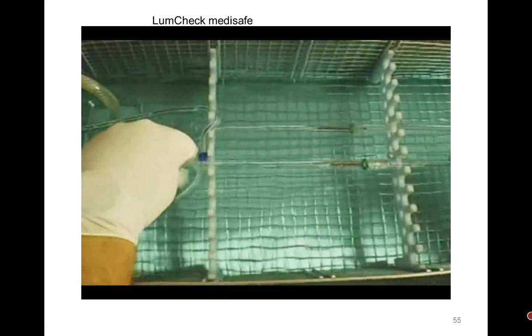So how do you check one that does lumens? Your pulse flow or retro flow, depending on whose you're using, they use different terms. Do you have a surrogate device that works properly? Does the test soil represent what you're cleaning? You must check to make sure it's working. So I am now going to run a video here that came off of YouTube by a company showing why you want to use some type of pulse flow sonic. And this goes back to Michelle Alfa's article. Watch this.